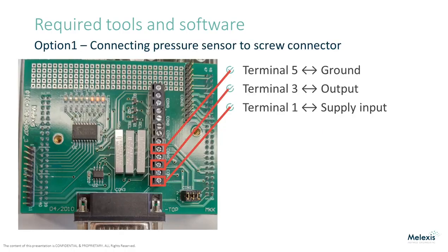Finally, a pressure sensor has to be connected to the daughter boards by its three application pins, which are the supply input, output and ground. There are two ways to connect those pins. The first option is to use the screw connector in the middle of the daughter board. The supply input of the sensor should be connected to terminal 1, the output to terminal 3, and the ground of the sensor to terminal 5.